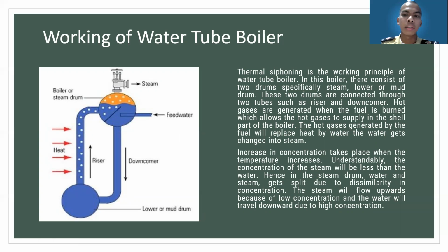Hot gas is generated when the fuel is burned, which allows the hot gas to be supplied to the shell part of the boiler. The hot gas generated by the fuel will transfer heat to the water. The water gets changed into steam. A decrease in density takes place when the temperature increases. Understandably, the density of the steam will be less than that of the water.